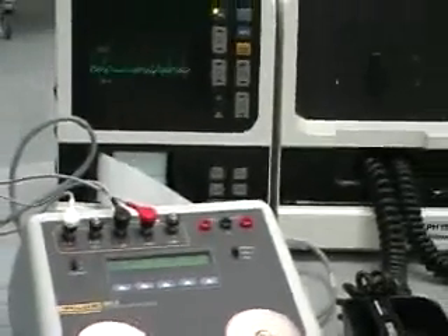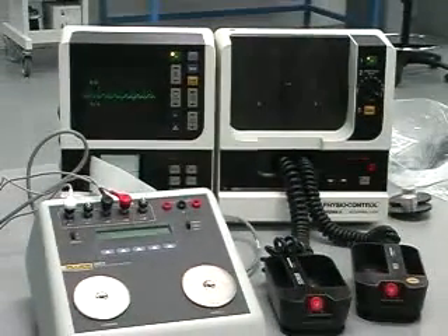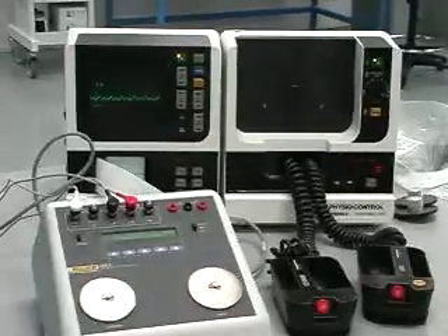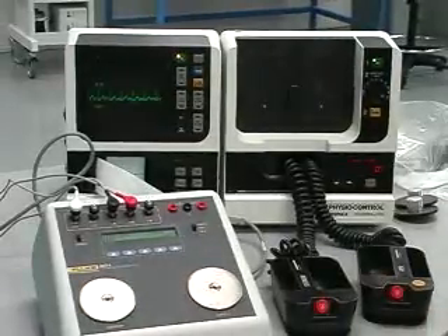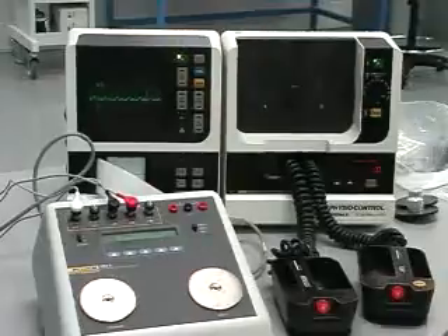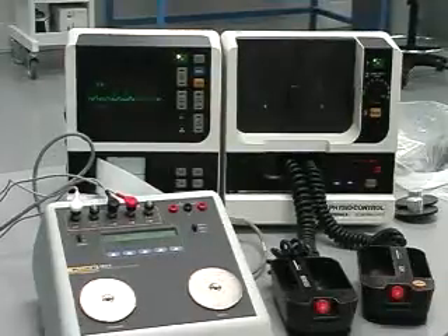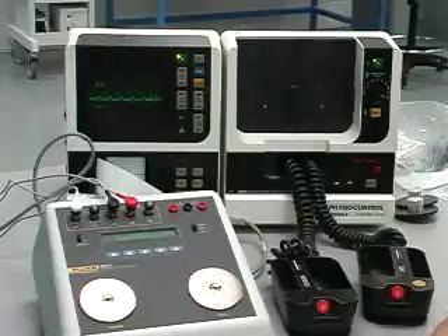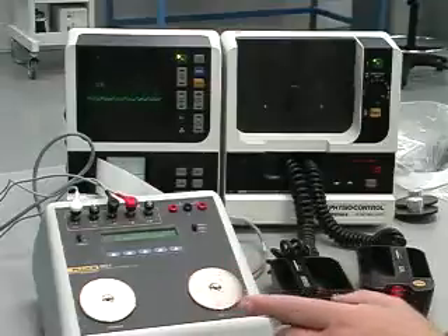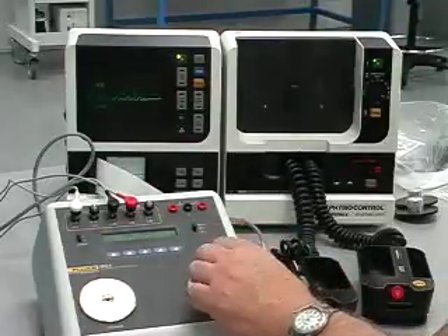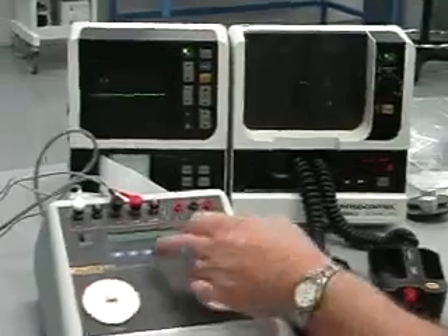And that is a test you would only do for a monophasic defibrillator, something that was spec'd by Physio Control quite a while ago. Not something that's really done much, but again, a good troubleshooting tool for the future. If you were to see defective readings or something out of the ordinary, you could push the button and see just what was there. Between looking at those readings and then going back to that wave menu, it would just give you something else to try.